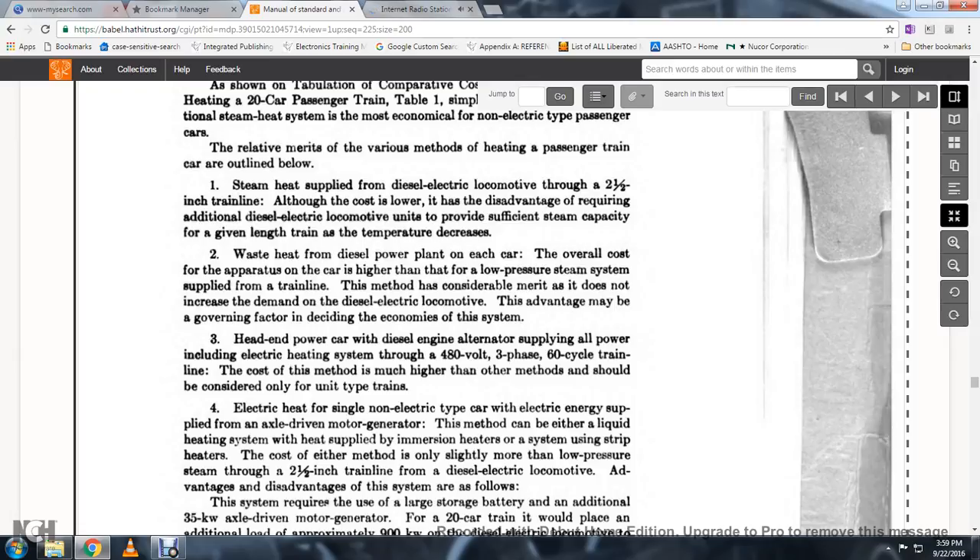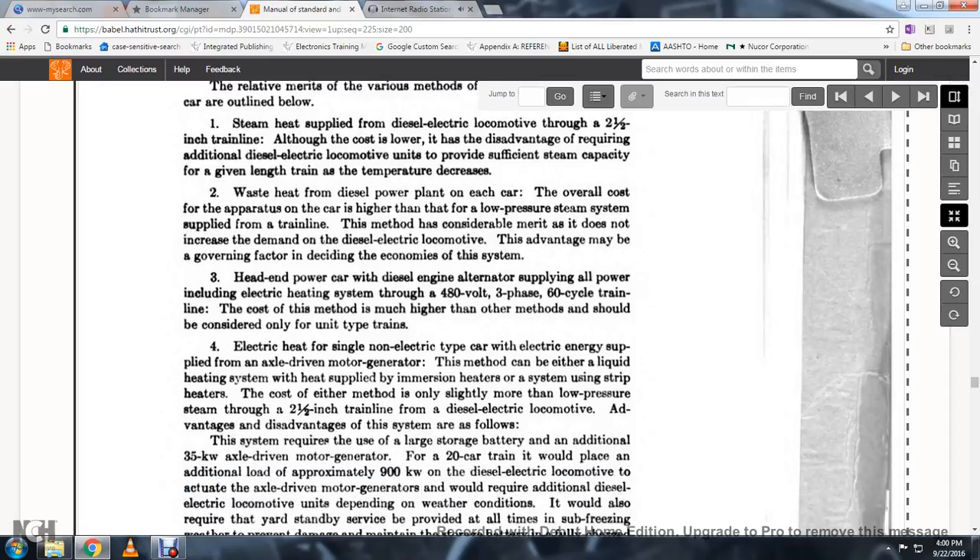Waste heat from the diesel power plant on each car: the overall apparatus cost per car is higher than that for a low pressure steam system supplied from the train. This method has considerable merit as it does not increase the demand on the diesel-electric locomotive. This advantage may be the governing factor in deciding the economics of the system. Head-end power from the diesel engine alternator supplying all power to the electrical heating system through a 480-volt, 3-phase, 60-cycle train line has an even higher cost and should be considered only for unit-type trains.